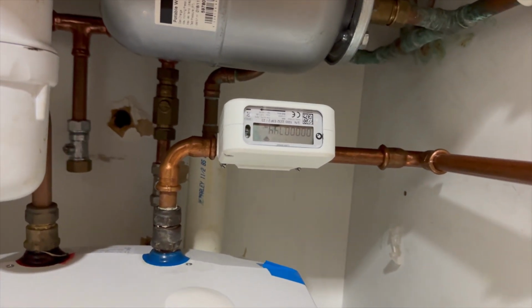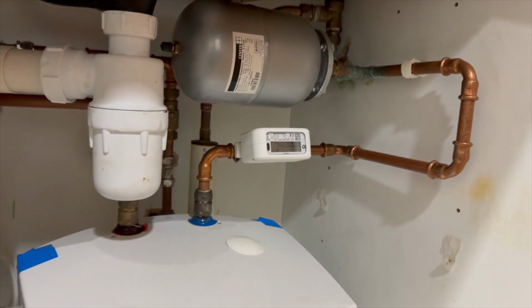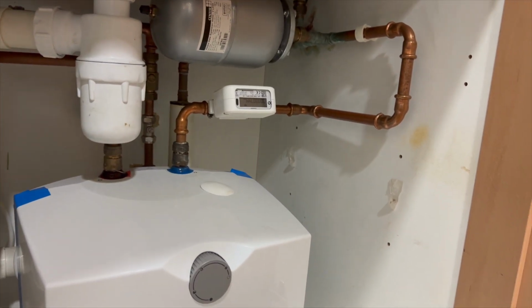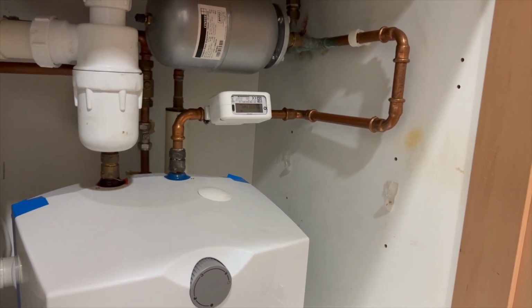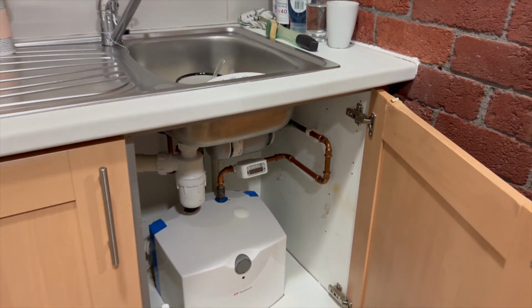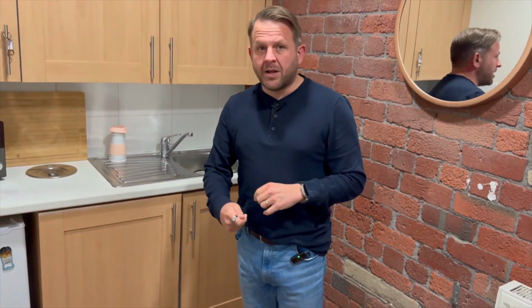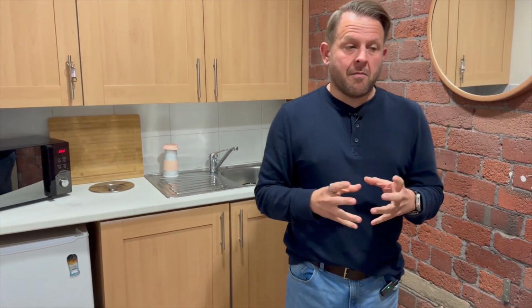there's a formula that's created to showcase Legionnaires. So if you have got a potential buildup of Legionnaires in a building, then this would start to notify you based on that through the platform. What normally happens in hospitals, in places that are looking for Legionnaires, is they send people around with dipsticks to measure the flow and temperature of the water and then manually work out what the risk of Legionnaires is. That takes that away. So operationally, it gives you better cost, all for a very small price tag to connect that to the device.